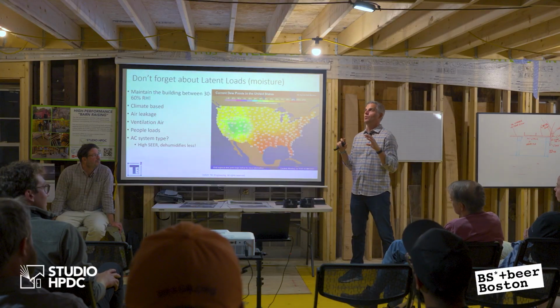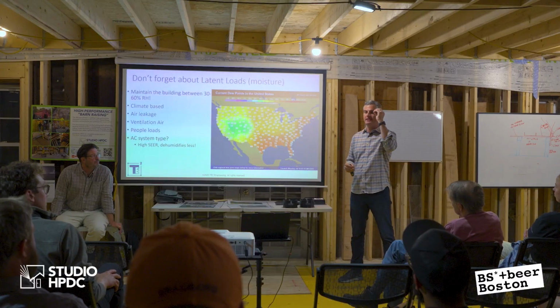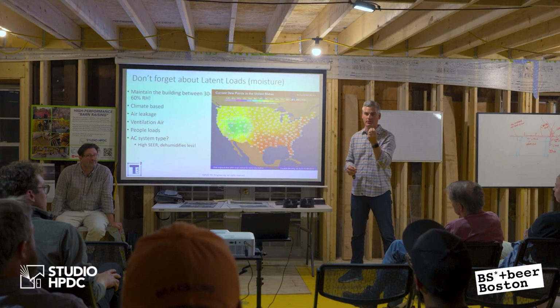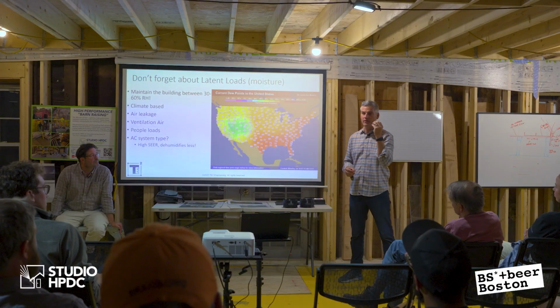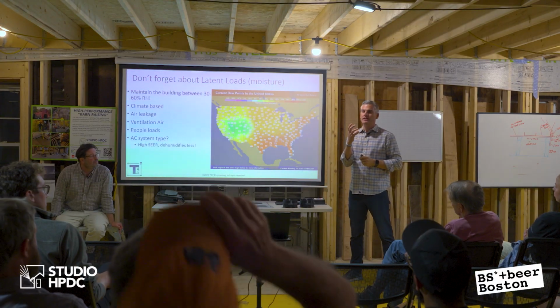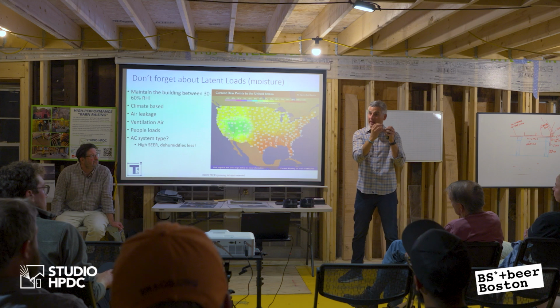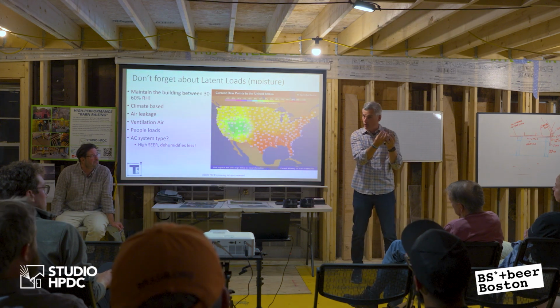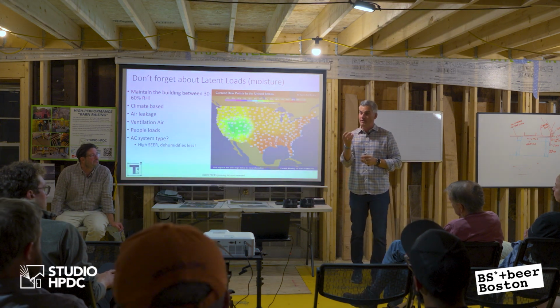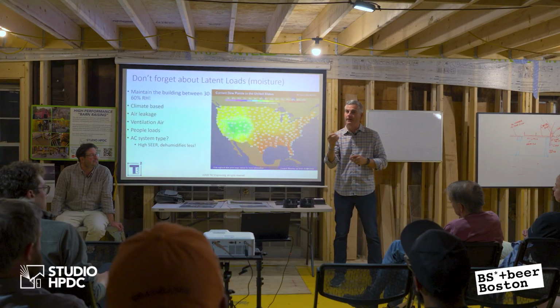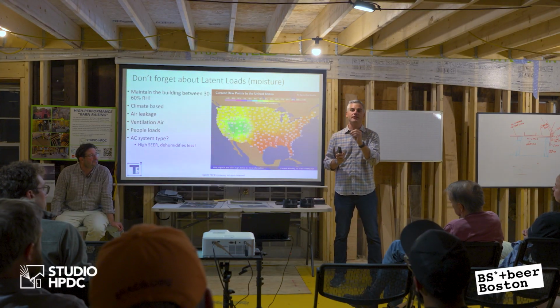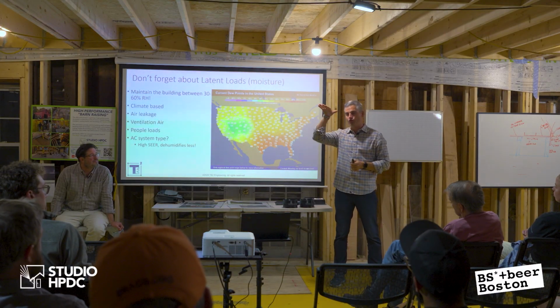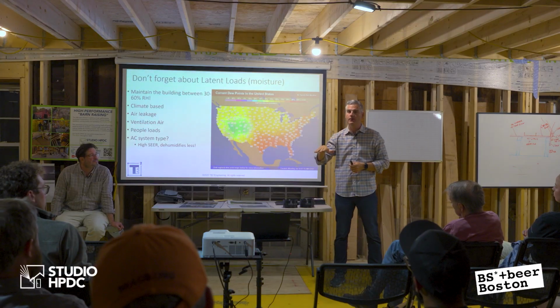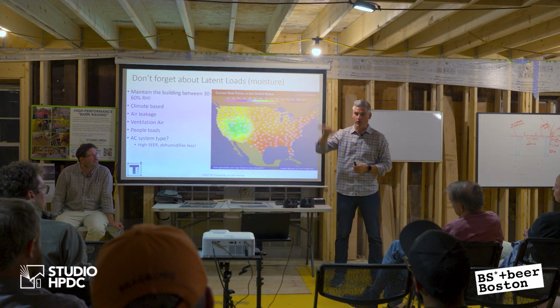So when we measure BTUs, right? Air has a sensible capacity to it, and it has a latent capacity to it. What I mean by that is that there's water vapor in the air. The air conditioning system sees both the kinetic energy of that air, meaning how much heat is in that air, the sensible aspect of it, but it also sees the water vapor in the air. We don't see it, but it's there, right? And so not all BTUs are created equal, in the sense that if a system has to run in cooling, I have to drop the temperature and I have to drop that water vapor. I have to dehumidify. And it's much harder to drop water vapor, much harder.